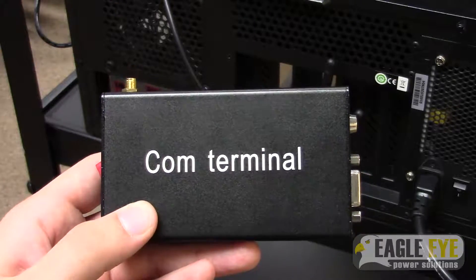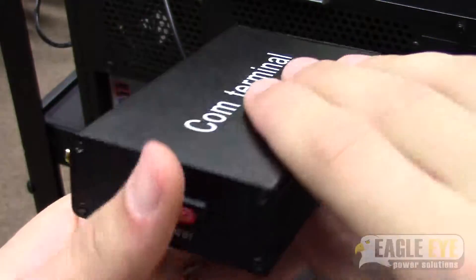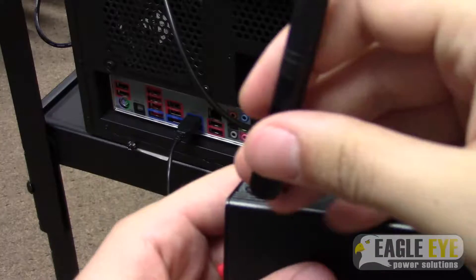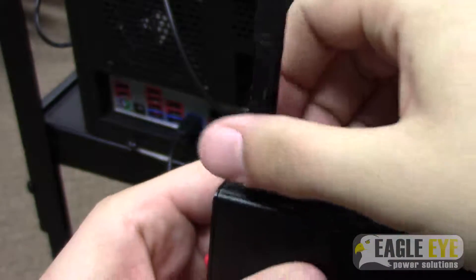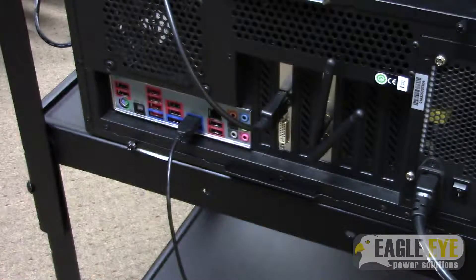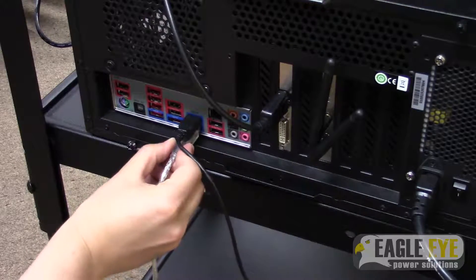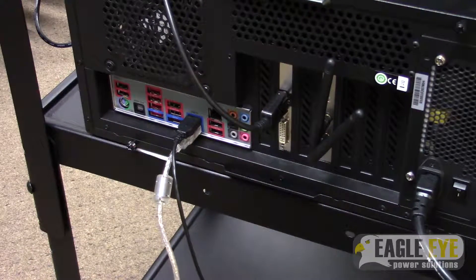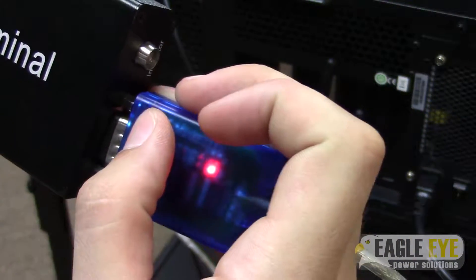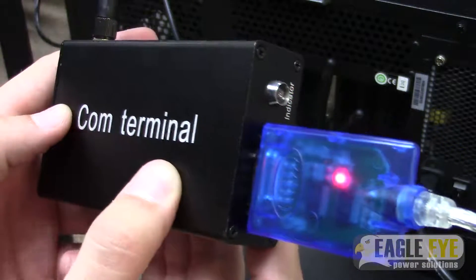The last step is to wirelessly connect your DACs to your load bank and to the com terminal. There are two antennas for wireless communication — one attaches to the top of your load bank, and the other attaches to the com terminal, as shown here. Once you have attached antennas to both, you can plug the com terminal into your PC using a USB to RS-232 cable. When you power the com terminal on, you will be ready to perform and monitor a discharge test with DACs.